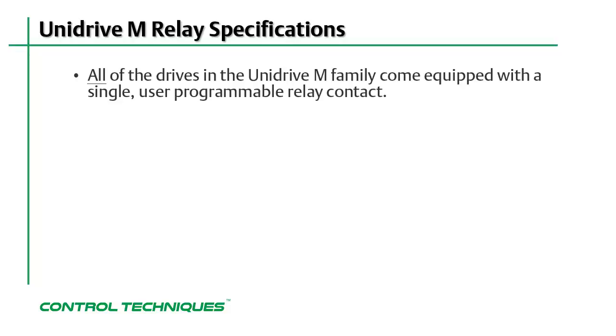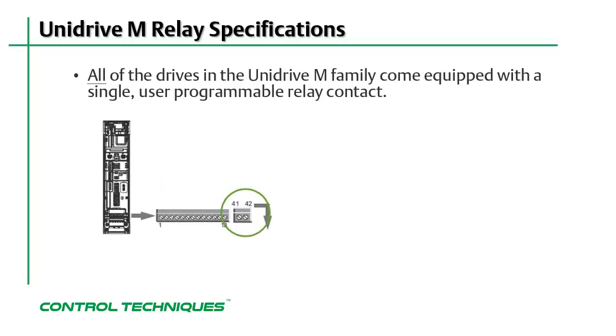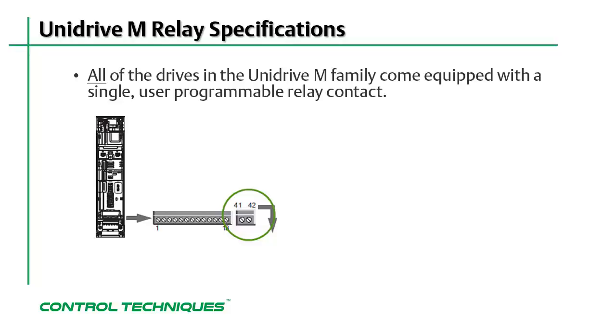The relay contact is wired into terminals 41 and 42. This is a dry contact relay, so the supply and load may be wired to either terminal.